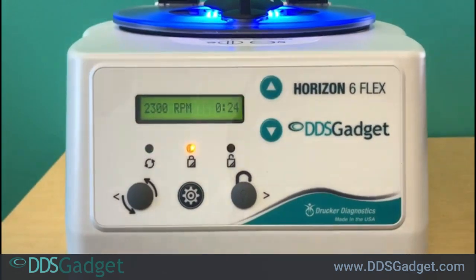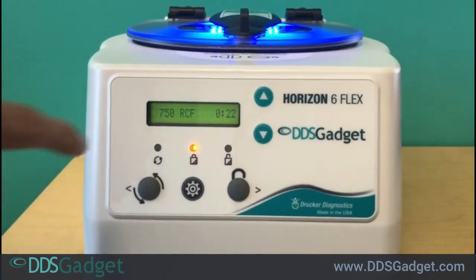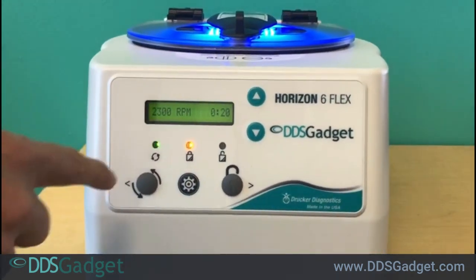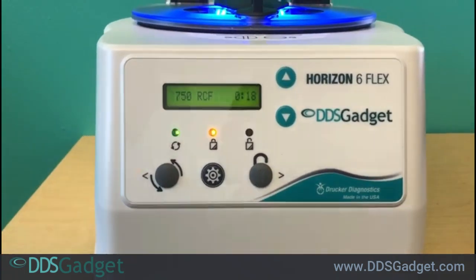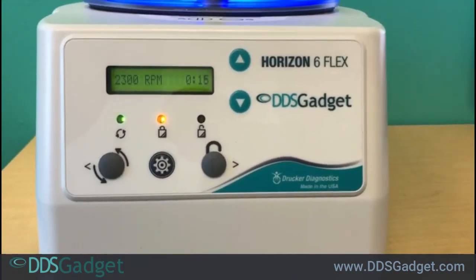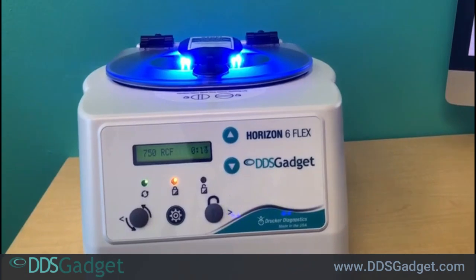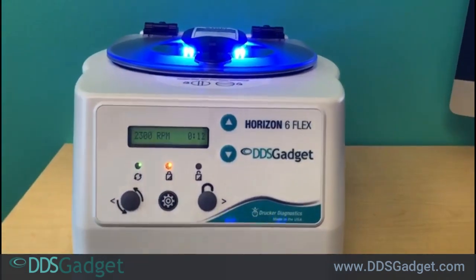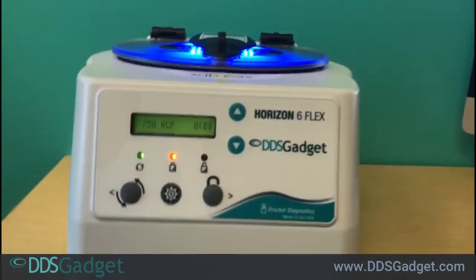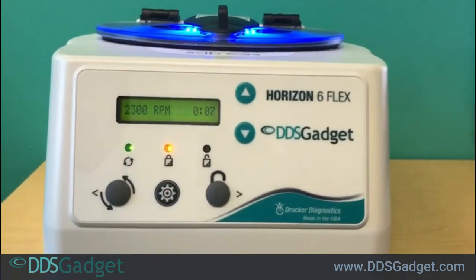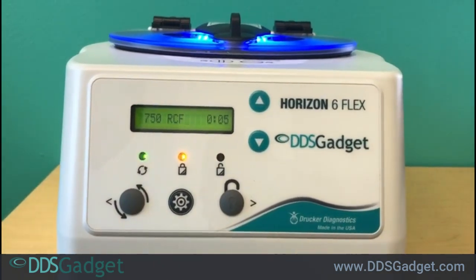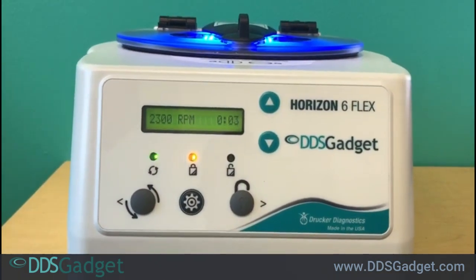So the centrifuge is about ready to finish the cycle. You can see again the time is running down. It's still showing that it's running. Again, it's very, very important not to open the centrifuge until it is completely stopped. And you'll see what happens when it stops. It first brakes, but it's not at a complete stop. So do not open the centrifuge while it's braking. You have to wait for a complete stop.